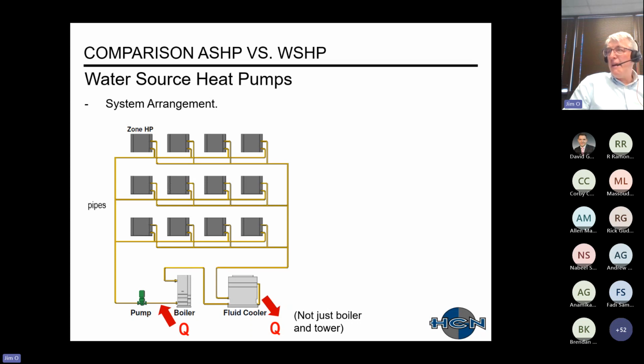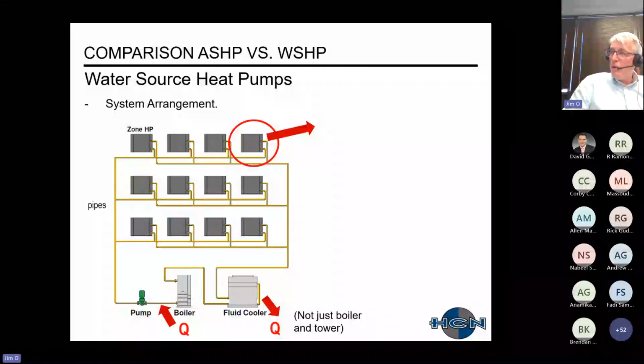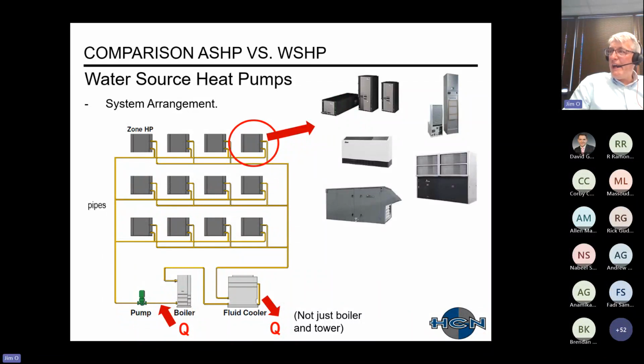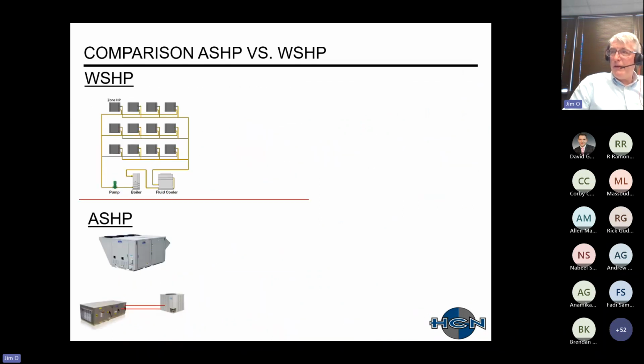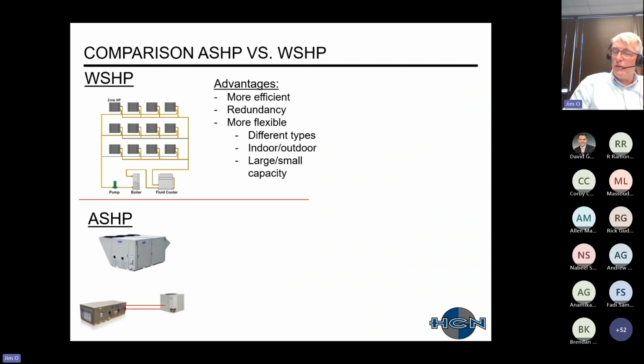And then with the water source heat pump, you have a lot more options in terms of your available systems. All right, and then just a quick comparison of pluses and minuses of water source heat pumps. Because you're using water, it's typically more efficient than air source. It eventually comes down to your heat transfer with wet bulb temperatures versus dry bulb temperatures. You'll be able to get much more redundancy with smaller units. You have more flexibility with the different types of units that are available.